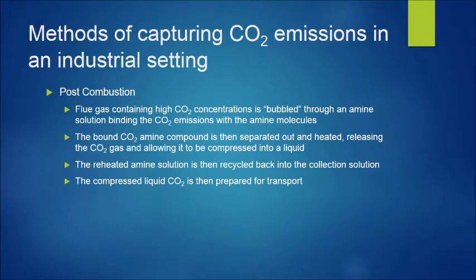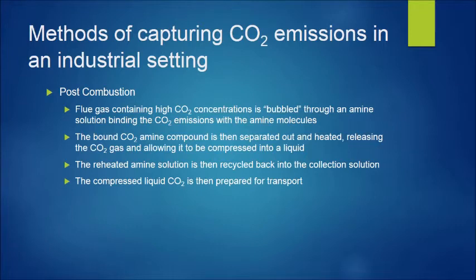However, higher concentrations of CO2 in the flue gas do make the process more efficient. Post-combustion capture occurs by bubbling the flue gas through an amine bath. The amine compounds bind to the CO2 and can be filtered out of the solution. After separating the bound CO2-amine compound, the compound is heated, releasing the CO2, which is then compressed into a liquid and prepared for transport. The now unbound amine solution is then able to be mixed back into the amine bath and will capture more CO2.